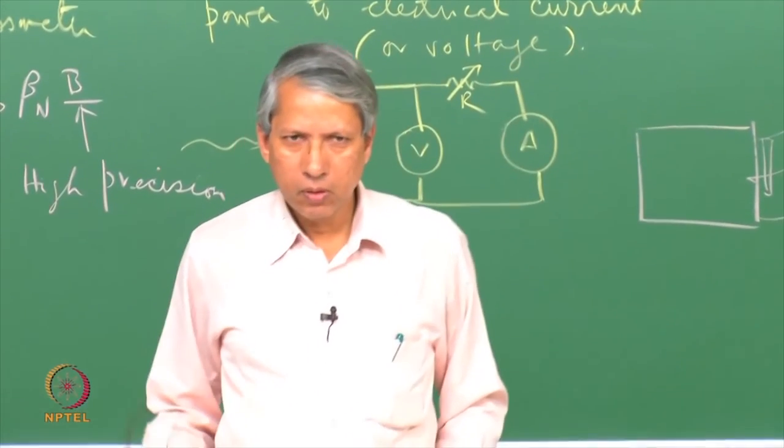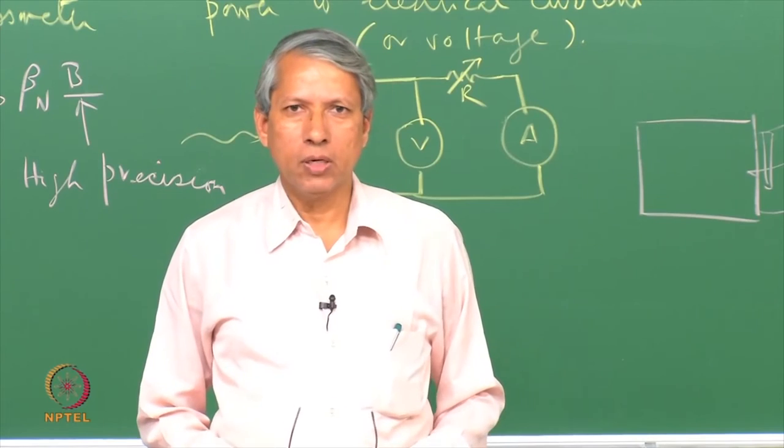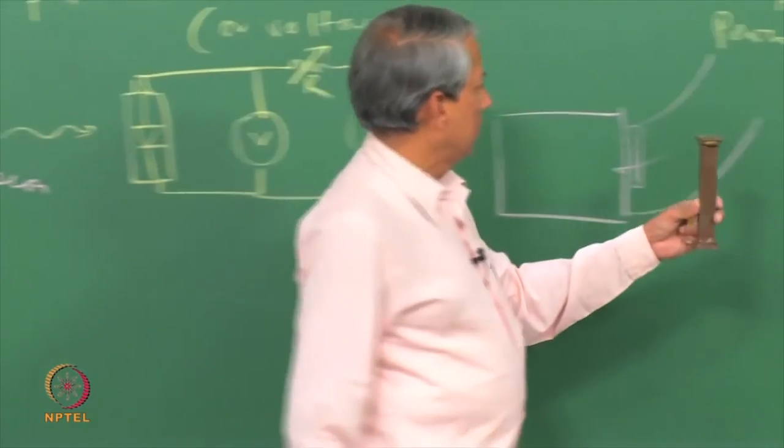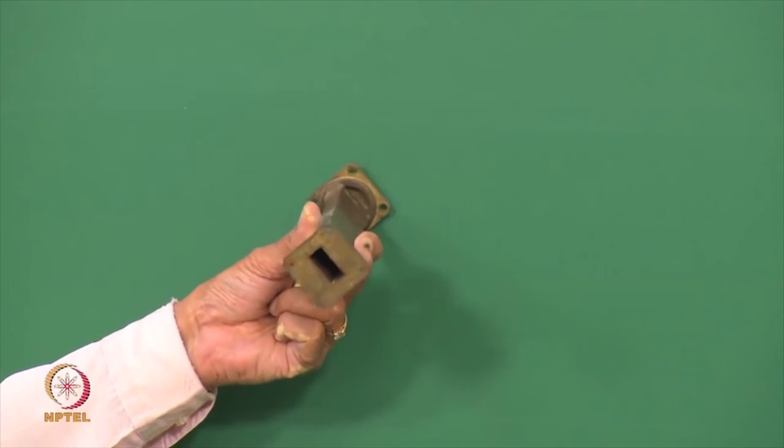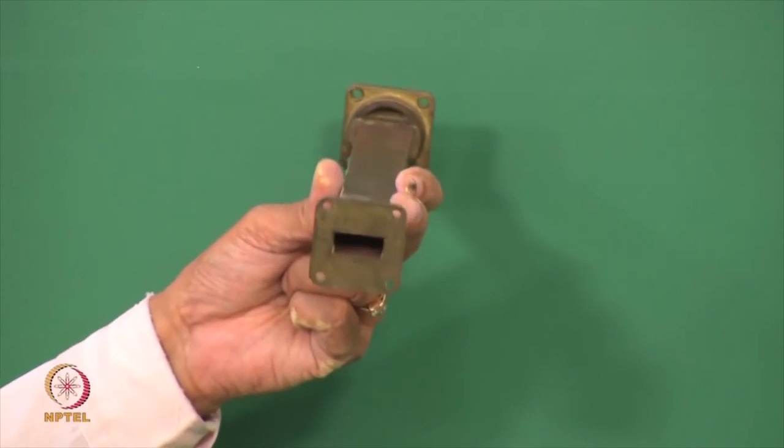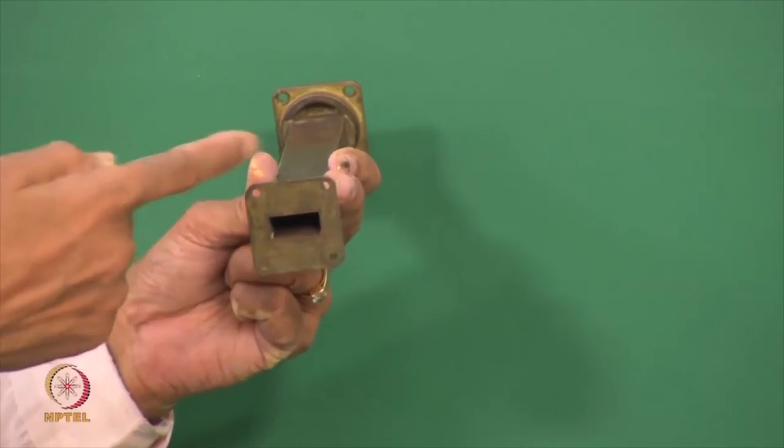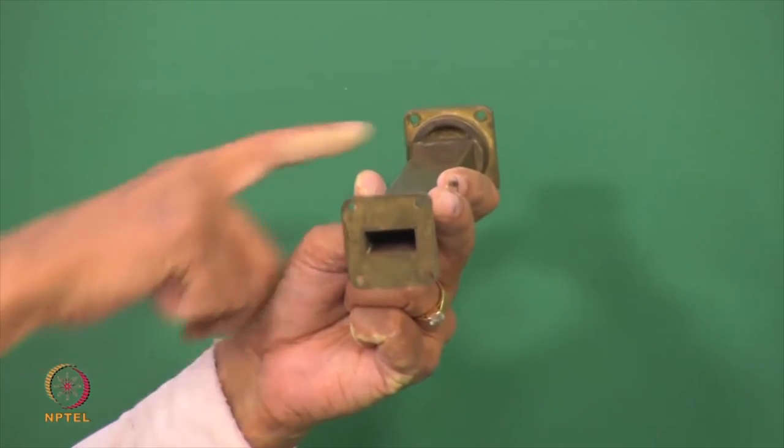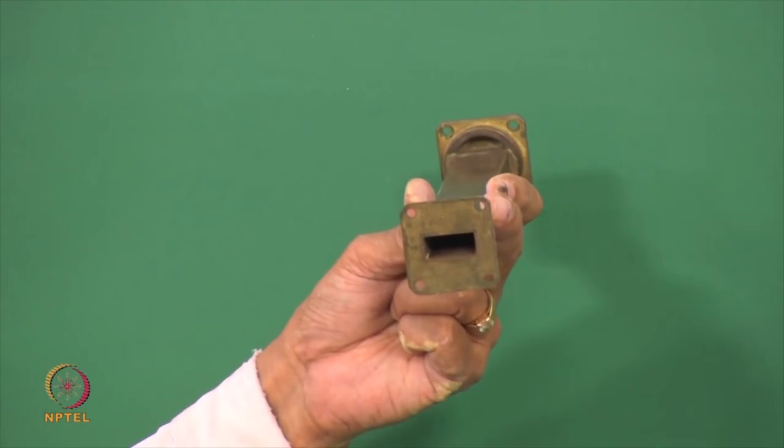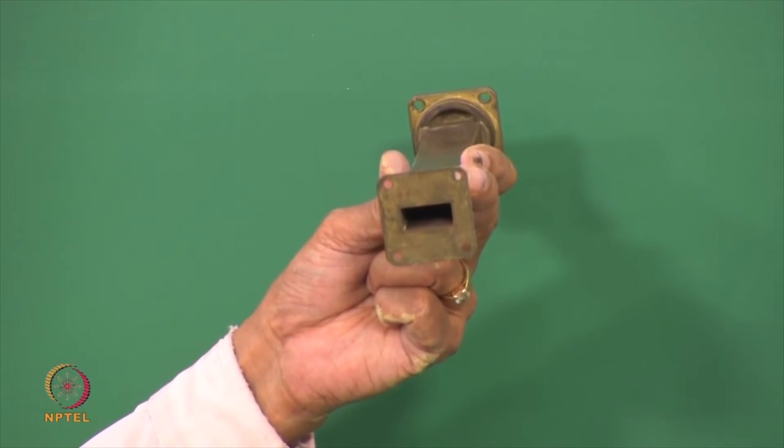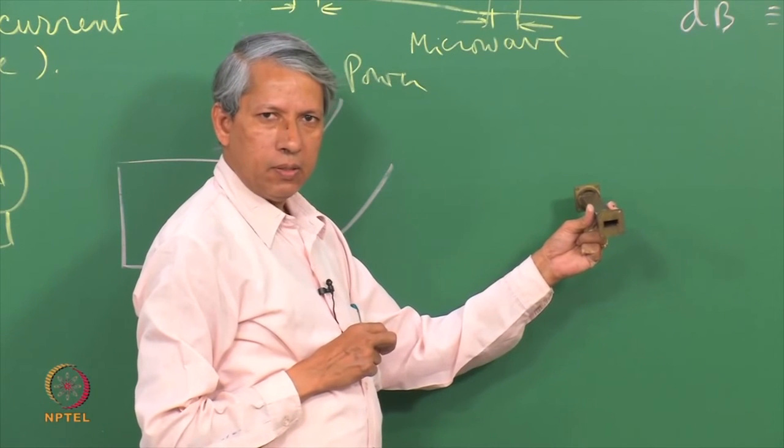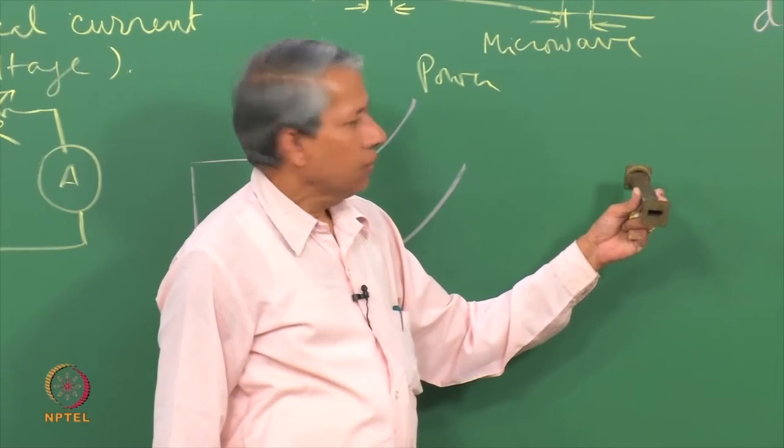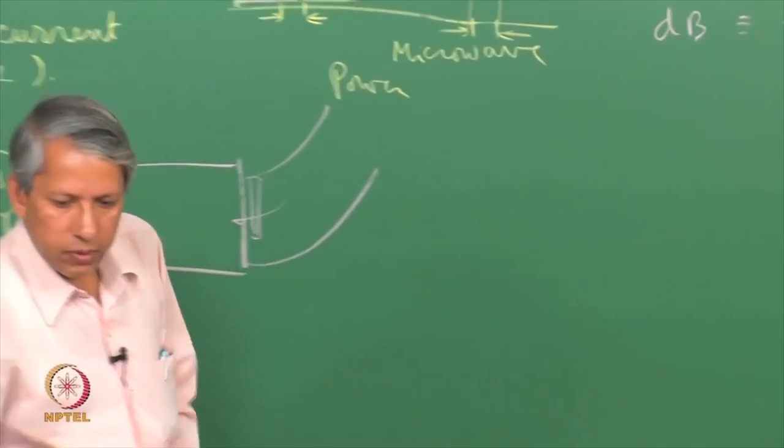Increasing crystal current, increasing bias increases the noise component. You cannot keep on increasing the bias in this fashion. You have to have certain compromise to get optimum sensitivity and optimum noise. With this we have covered all the major components of an EPR spectrometer. Before I conclude I would like to introduce a unit of measuring these various characteristics of microwave components and microwave power and this unit is called the unit of attenuation or amplification which is called dB. dB stands for decibel.